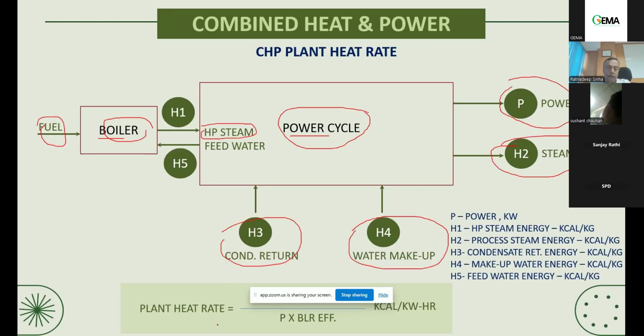So if you see the plant heat rate calculation, then you will find the plant heat rate is a function of all these outputs and inputs. If you see the input and output formula, the output is the power, and in the top portion it will be the input, that is your HP steam energy, less the feed water which is going to the boiler. And again the condensate return, there will be a small heat coming to the system, and the makeup water, some small heat coming to the system. So if you do the arithmetic out of it, you will get the plant heat rate.